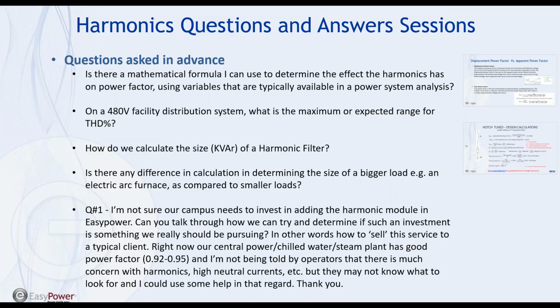And it would be very difficult to evaluate the change without having a tool like this Harmonic Analysis package. So a simple change such as adding a capacitor bank to the network would be an example of something that would suggest that you should go out and purchase the software package so that you could then evaluate the impact of that capacitor bank on the network. The installation of a large VFD drive would be another case. But when you have a facility that's not experiencing problems, I'm sure that your boss will ask the question, well, what's the payback? And you may not be able to justify it in that regard.